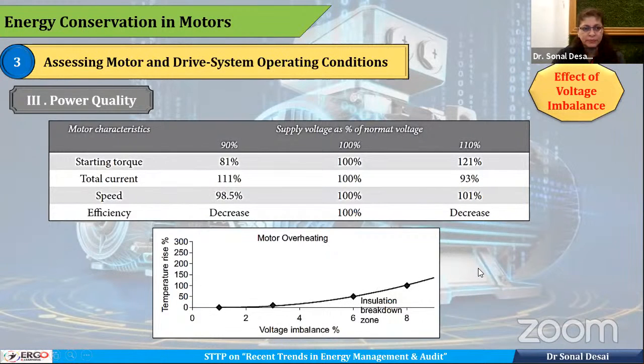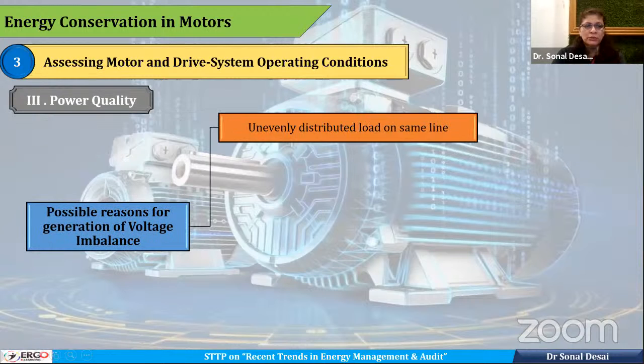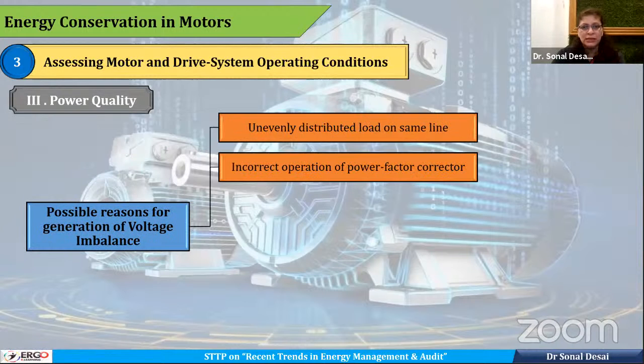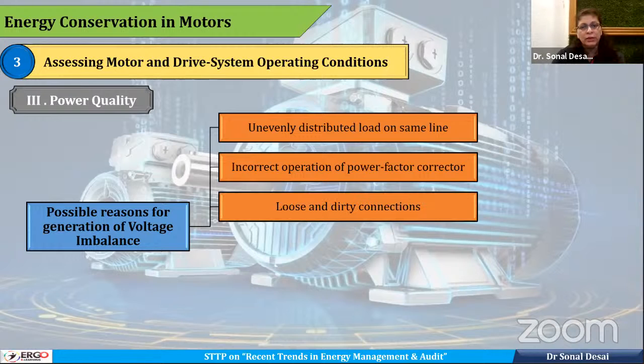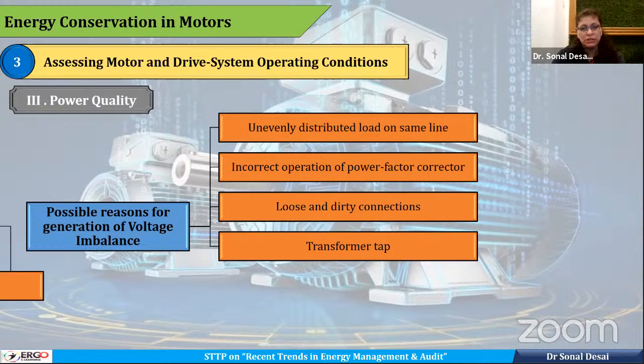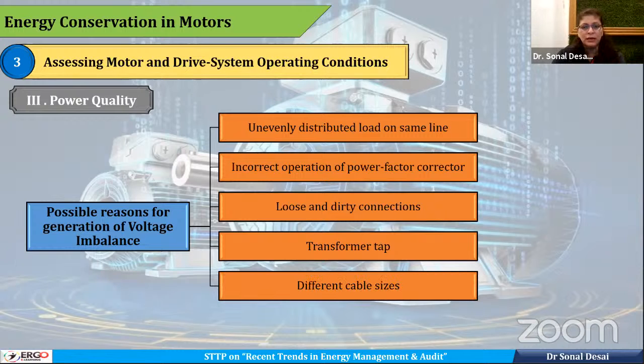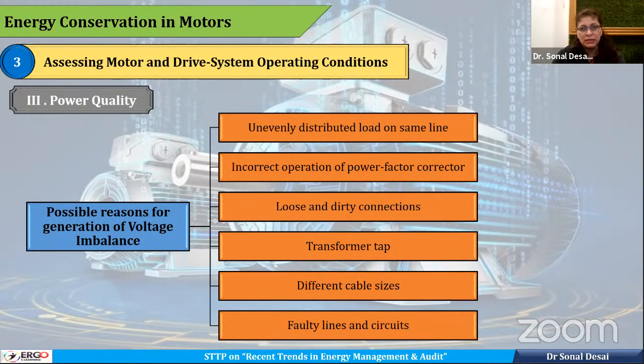So possible reasons for imbalance are that there can be unevenly distributed load on the same line, so redesign them. There can be incorrect operation of the power factor corrector. There can be loose or dirty connections. A transformer tap issue, or different cable sizing in the same line, or there can be a faulty line or faulty circuits.